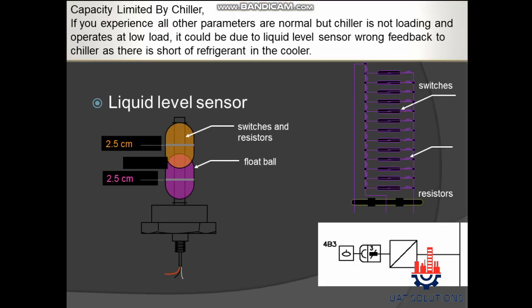Capacity limited by chiller: If you experience all other parameters are normal but the chiller is not loading and operates at low load, it could be due to the liquid level sensor giving wrong feedback to the chiller, as there is a shortage of refrigerant in the cooler.